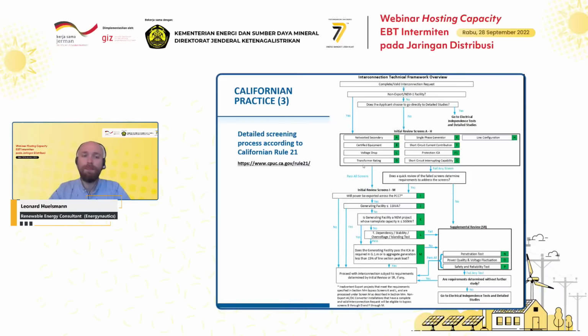This entire screening process is defined in California in the so-called Californian Rule 21. You can see the link here below where you can see the exact technical regulations. It's all public. And this is the process. You see not only the screens that I have shown, so there was screen D with the transformer rating, and if it failed any screen, you would do the supplemental review, and then you would have the hosting capacity assessment screen. But you have also these other types of screens, which look at other aspects. For example, at a certain size, maybe it must be three-phase connected, or other aspects of this entire process.